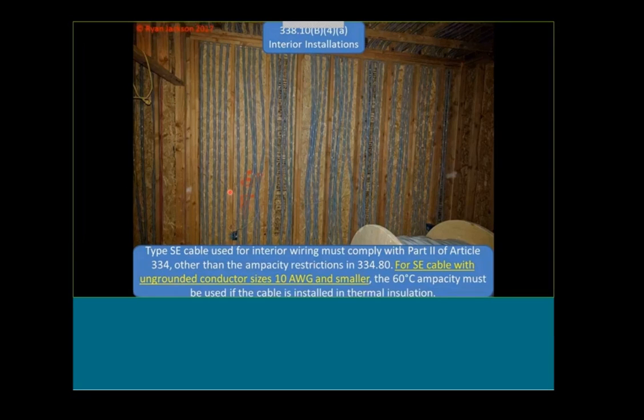In previous editions, the rule said that if you put this wire in a wall or ceiling and insulate it, you have to pretend those cables are only good for 60 degrees, even though they're not. We changed that in 2017.